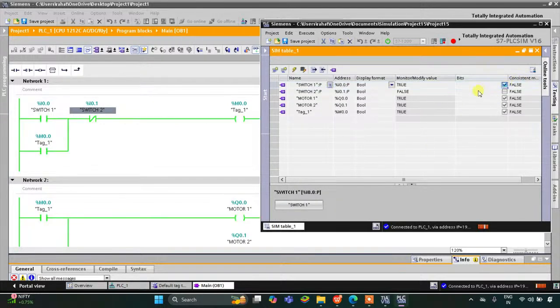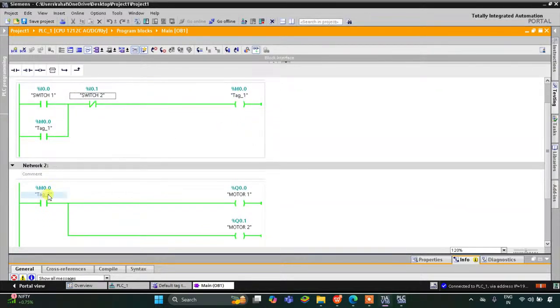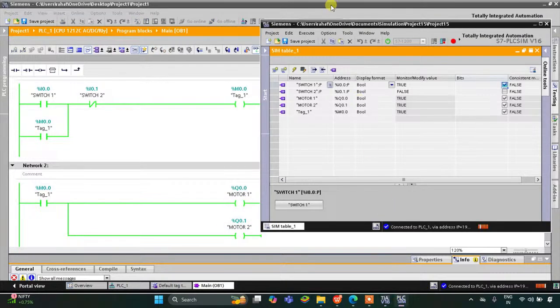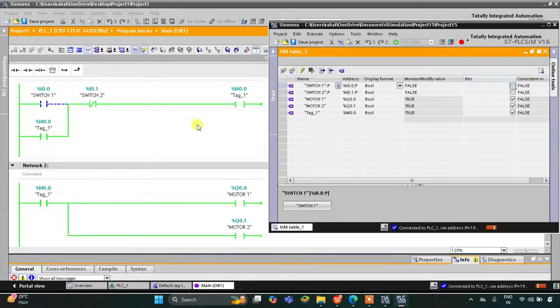When I turn on Switch 1, M0.0 gets true, and when M0.0 gets true, Motor 1 and Motor 2 turn on. Then when I turn Switch 1 off, due to latching M0.0 is still true. The current flows through it, Switch 2 is in false state, and as it is a normally closed contact the current flows through it. As a result M0.0 remains on, which in turn keeps Motor 1 and Motor 2 on. These motors still remain on.